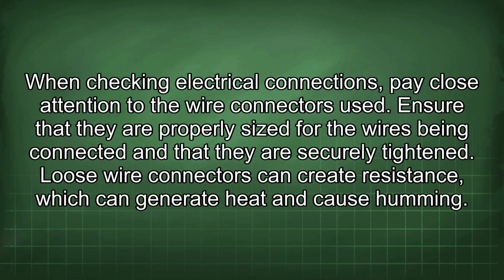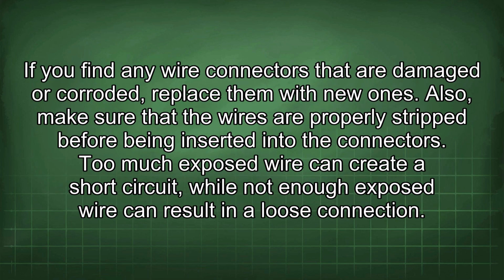When checking electrical connections, pay close attention to the wire connectors used. Ensure that they are properly sized for the wires being connected and that they are securely tightened. Loose wire connectors can create resistance, which can generate heat and cause humming. If you find any wire connectors that are damaged or corroded, replace them with new ones.